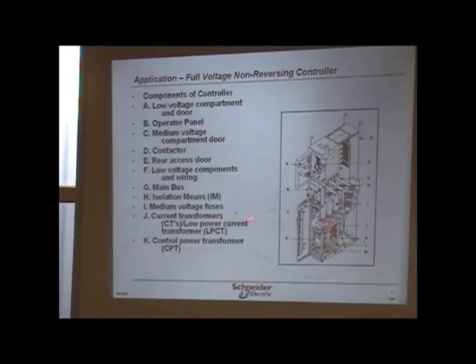This shows it illustrated, and for example right here it's saying this is the isolating means, right here at H, and that's what IM stands for, isolating means. G is the main bus, and you can see those three phases right there where it comes in, and it ties into the other section, so it could be a standalone, or you can have more than one of these switches in there, so you have a common feed coming in that ties into them.